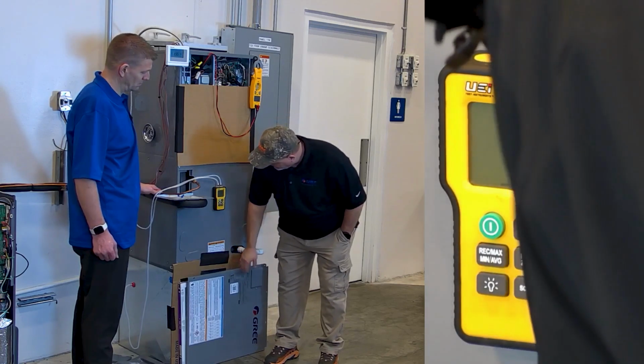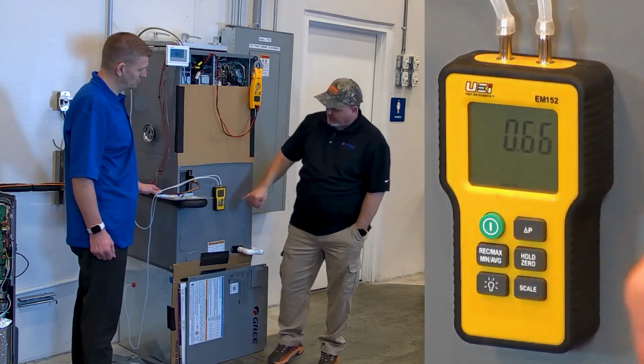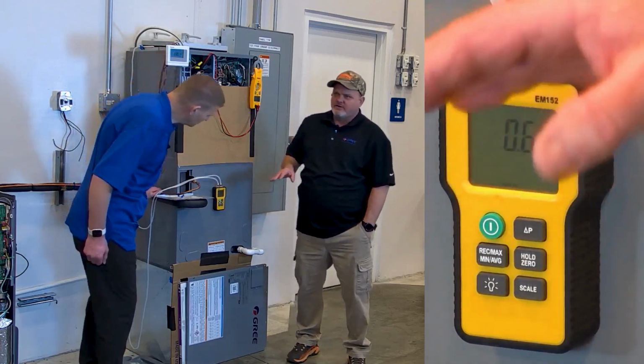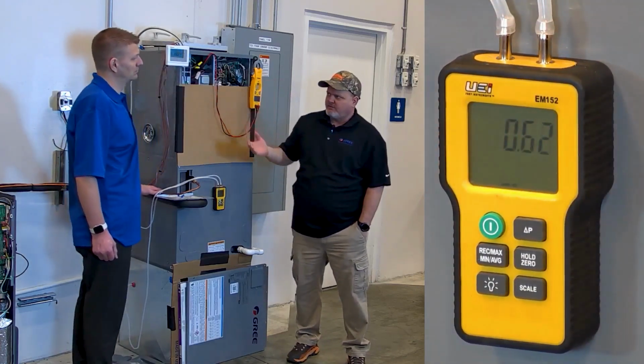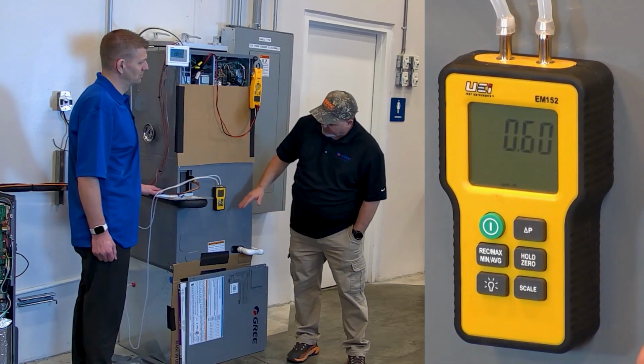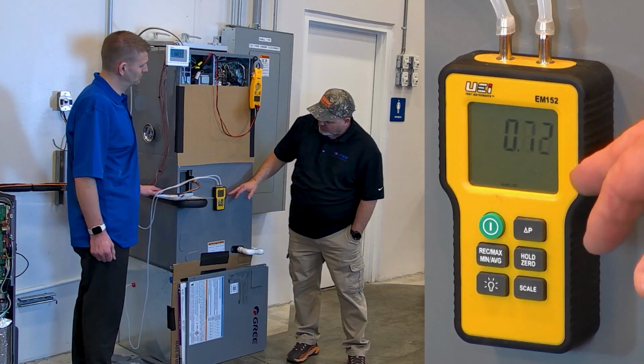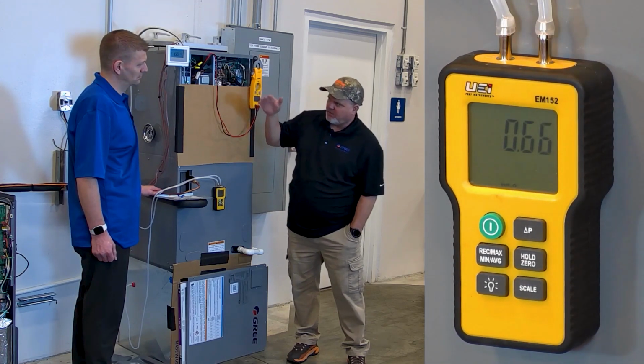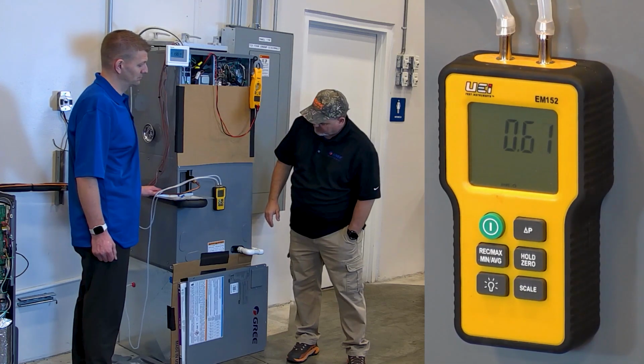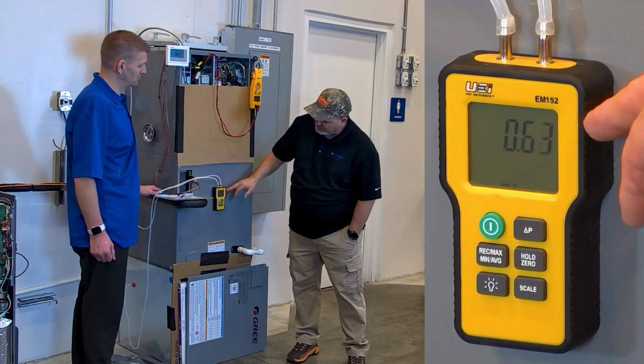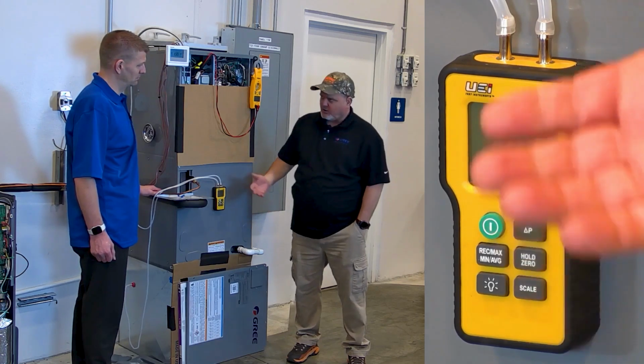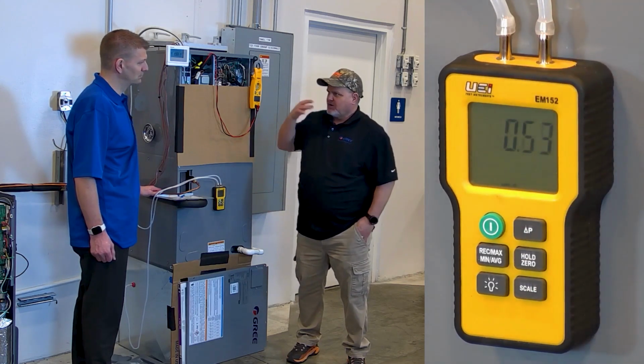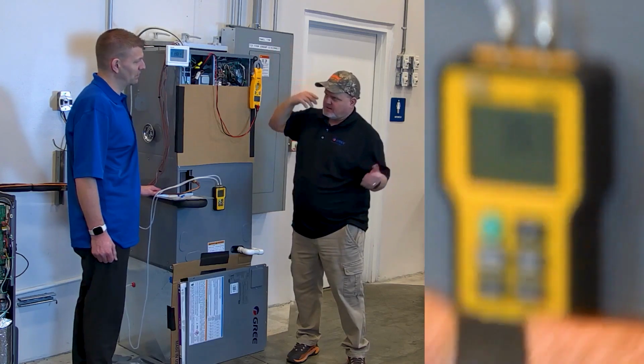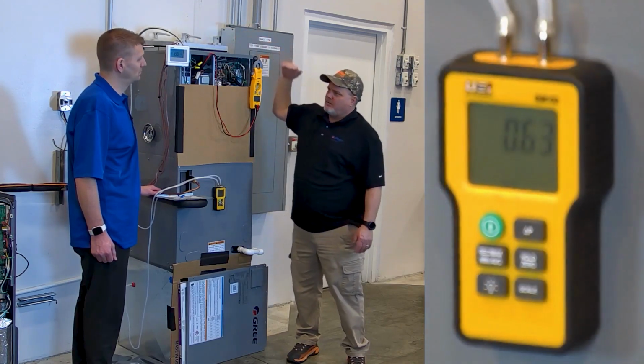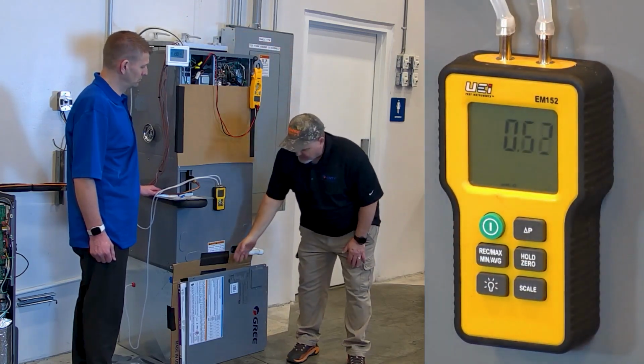That jumped it up. See, I don't like it going that high. Even though you see it around that 0.66, then it goes to 0.75, then it drops back down. The thing is though, you don't want to see it going up into that 0.75. My guess is that bouncing around so much could have a lot to do with turbulence too, because we don't really have a pressurized duct system, like I said, and we're putting the thing right on top of the blower. So it's not the same as doing it in the field.